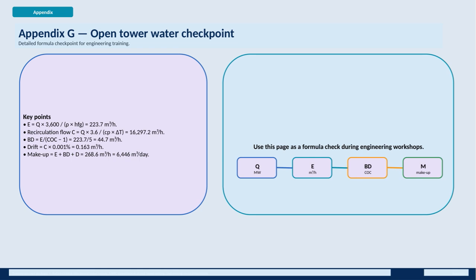Then blowdown, BD, is calculated by dividing evaporation E by the cycles of concentration minus 1, here resulting in 44.7 cubic meters per hour. This represents the water discharged to control mineral buildup. Drift loss, a small fraction of the recirculation flow at 0.001%, equals about 0.163 cubic meters per hour, accounting for water droplets carried away with the exhaust air.